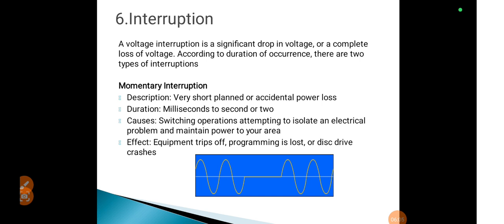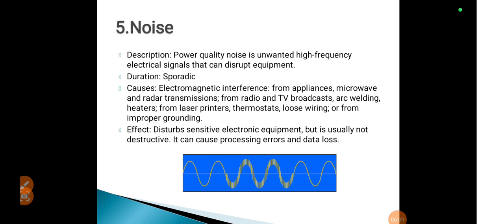The next is noise. What is noise? Noise is an unwanted high frequency electrical signal that can disrupt the equipment. The different causes of noise are electromagnetic interference, television diffusions, radiation from welding machines, arc furnaces and electronic equipment. Improper grounding may also be a cause of noise. The different consequences of noise are disturbance of sensitive electronic equipment, and it may cause data loss or data processing errors.